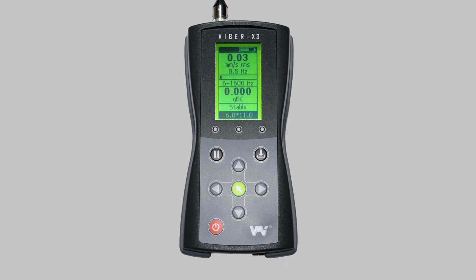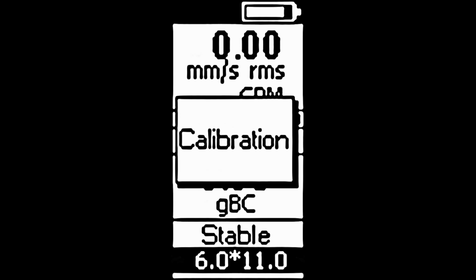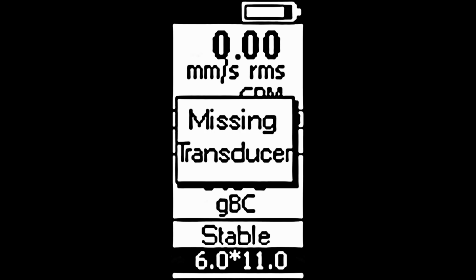While you are taking measurements, your device may display 1 of 4 warning messages. Number 1. Calibration. This message will display only once, then the defaulted calibration data will be used by the device. This does, however, lower the accuracy of the readings, and VMI recommends calibrating the device as soon as possible. Number 2. Missing transducer. This will display if there is a fault with the transducer or its cable. It can also occur if you are using an external power source for the transducer. If so, you need to disable the transducer power setting. Remember, this will enable every time the device is turned on.